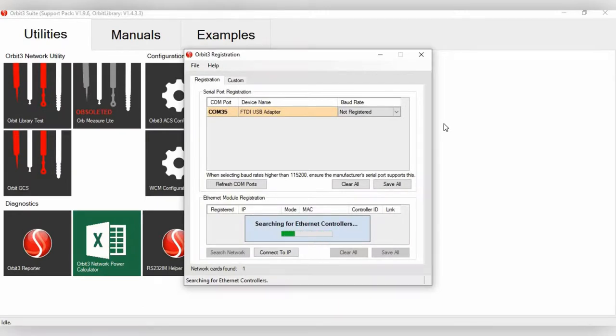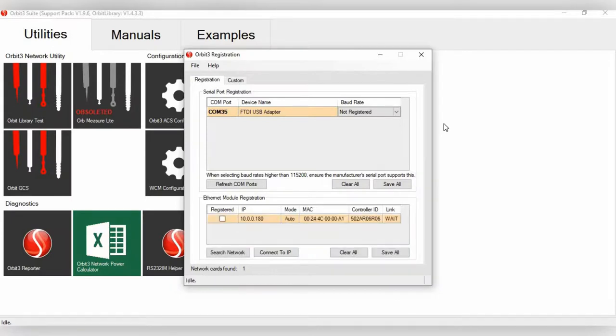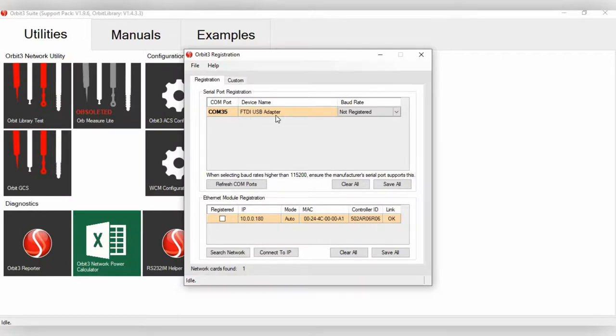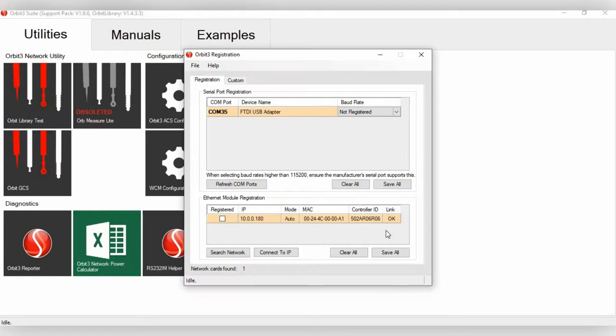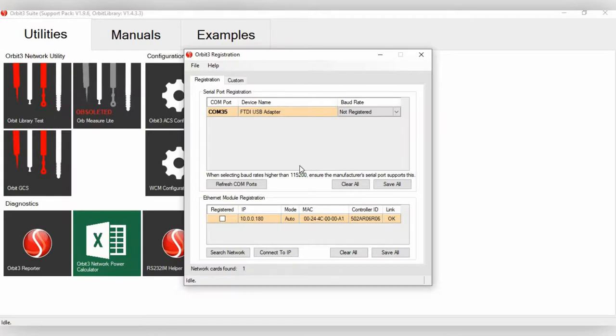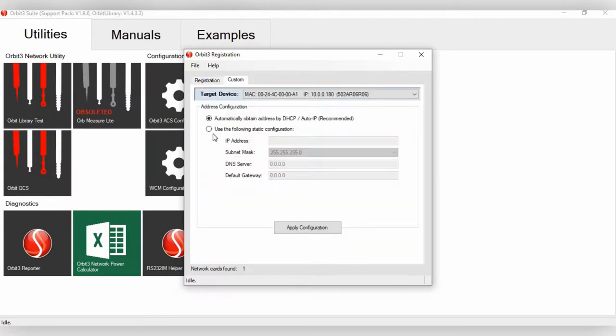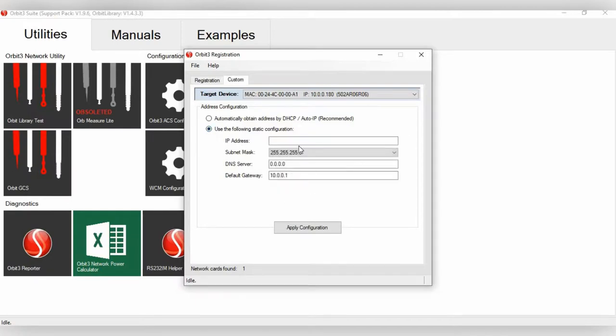So first, I have a USB Interface Module plugged into my computer. And as you can see, for the serial port registration, it virtually set up a COM port for the USB adapter. If you have an RS-232 Interface Module, that will be listed up here, and that will set up a COM port as well. Then down here, here is the Ethernet Module Registration. Here is the IP address, the MAC ID that you will also see on the Ethernet IP Interface Module as well. Another thing you can do as well, if you click Custom, you can actually create your own IP address by just clicking here and then entering your own particular configuration.